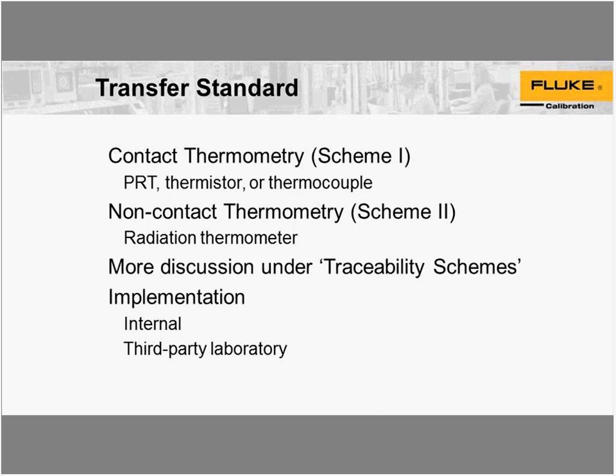The transfer standard is basically how you get traceability for your thermal radiation source. This transfer standard can take one of two forms. It can come through contact thermometry — the transfer standard is a PRT, a thermistor, or a thermocouple. It can come through non-contact thermometry — in this case the transfer standard is a radiation thermometer. We'll talk more about this under traceability schemes.